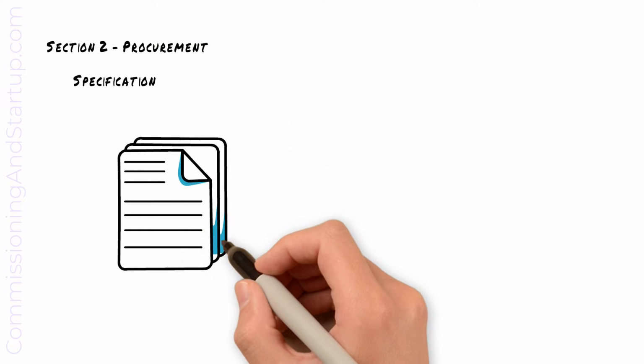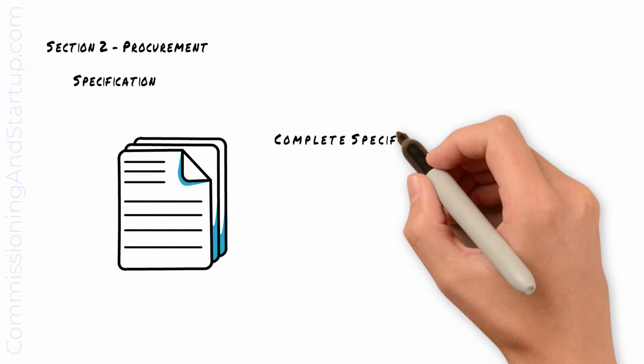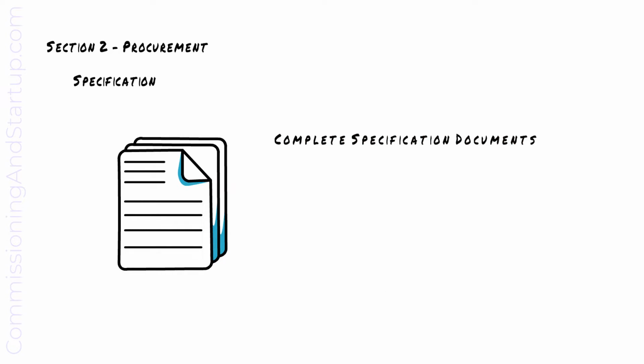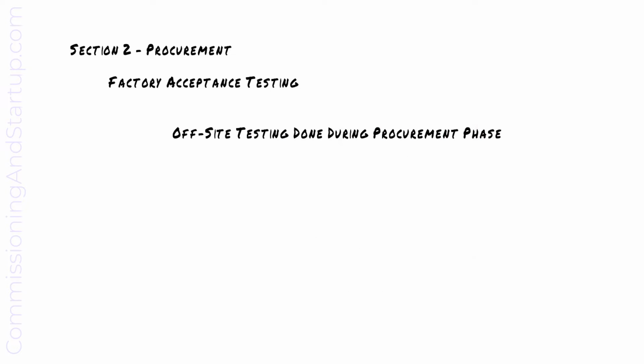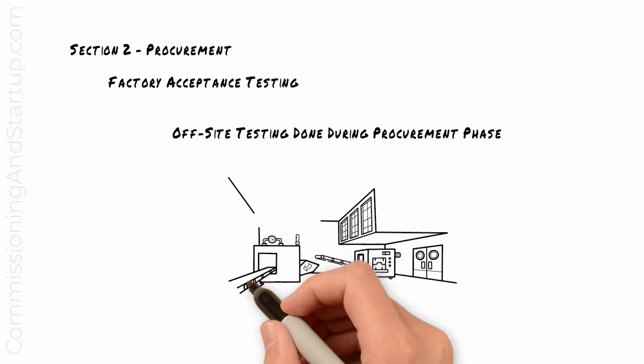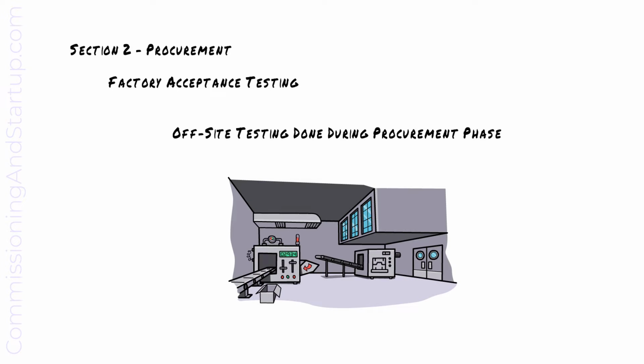Prior to procurement during the design phase, a detailed specification is prepared defining all the technical requirements of the project, including the factory acceptance test requirements. Factory acceptance testing is the off-site testing done during the procurement phase in the factory to verify that the software and hardware are designed correctly and meet the specification requirements.